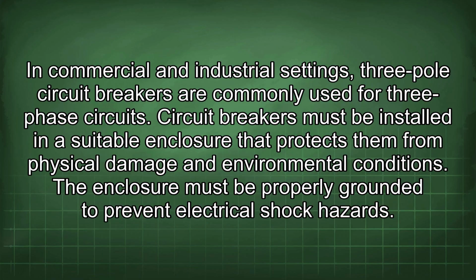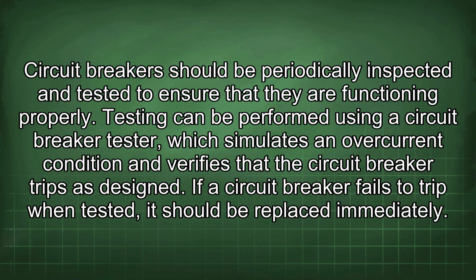Circuit breakers must be installed in a suitable enclosure that protects them from physical damage and environmental conditions. The enclosure must be properly grounded to prevent electrical shock hazards. Circuit breakers should be periodically inspected and tested to ensure that they are functioning properly. Testing can be performed using a circuit breaker tester, which simulates an overcurrent condition and verifies that the circuit breaker trips as designed. If a circuit breaker fails to trip when tested, it should be replaced immediately.